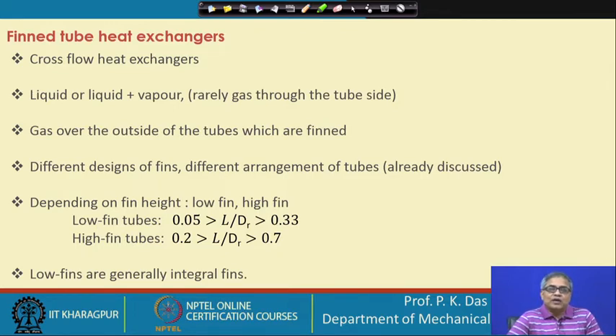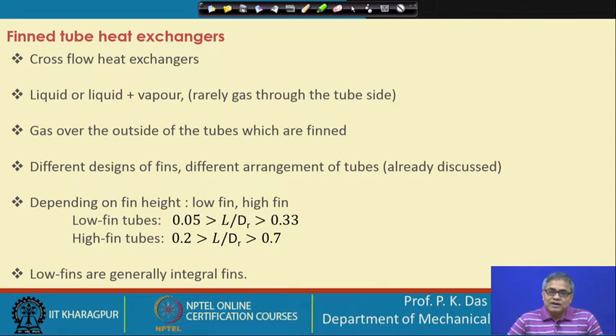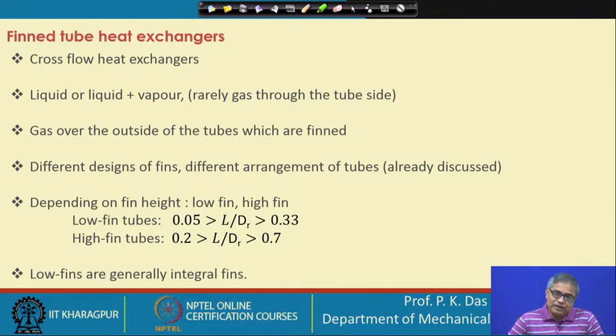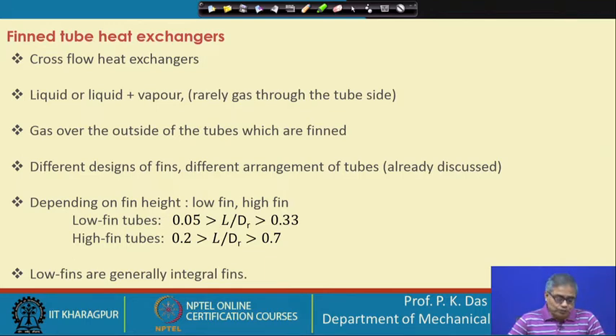Low fin tubes are used in many cases such as condensation, where outside the tube you need phase change heat transfer. More than increasing surface area, these fins perform other duties — they can enhance the rate of heat transfer in phase change heat transfer in a unique role. Low fins are generally integral fin tubes, as already mentioned.